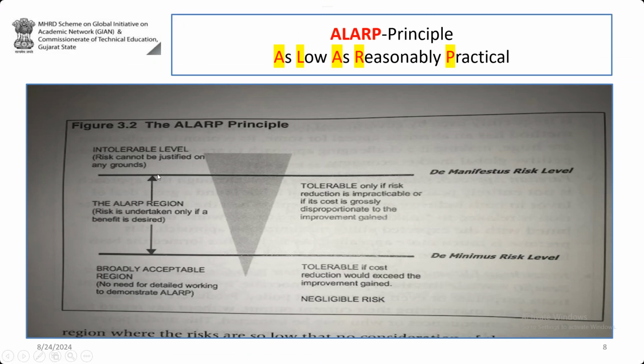Once you reduce the risk, because this line is the maximum level of risk, when you reduce the risk below this line, then it becomes an acceptable region. From this to this, all is acceptable region, meaning the risk is tolerable. It's a tolerable region. When you go below this line, this is the minimum risk; this is minimum risk, this is maximum risk. Below this, risk is not required to be reduced because it is a broadly acceptable region. So our SIF, our SIS, everything should be designed for this region, that is the ALARP region.